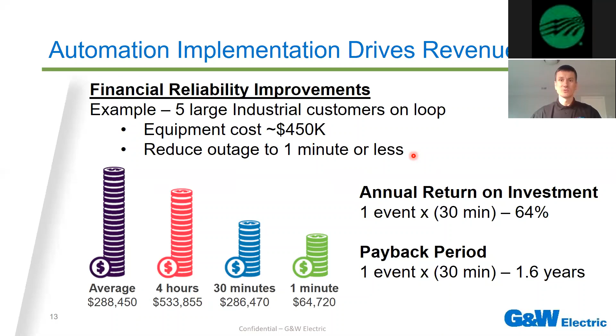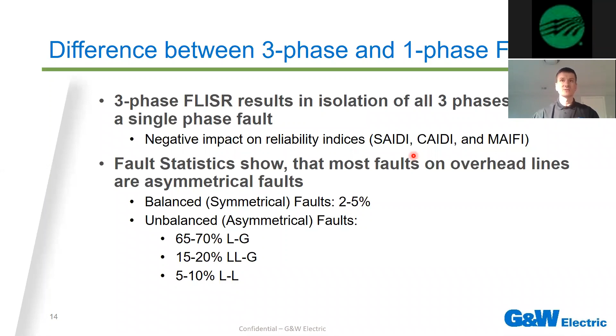Before moving into the communication aspect, I wanted to make a point on single-phase FLISR. Everything we just looked at with that graph was 3-phase FLISR, meaning if you have a fault on a phase - most likely, as statistics show, a line to ground fault up to 65 to 70% of the time - you essentially trip out all 3 phases. If you have residential loads on those 3 phases, the loads fed by phase B and phase C are being affected by that A phase fault. With single phase FLISR, you basically eliminate that and isolate only the phases affected by the fault, which makes a huge improvement on your reliability numbers.